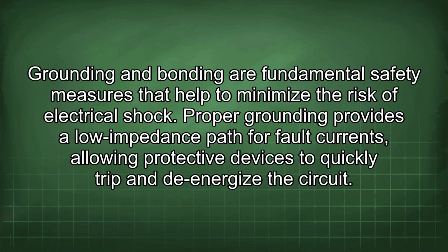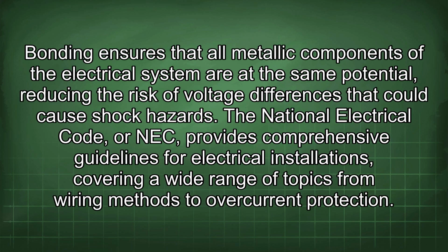Grounding and bonding are fundamental safety measures that help to minimize the risk of electrical shock. Proper grounding provides a low-impedance path for fault currents, allowing protective devices to quickly trip and de-energize the circuit. Bonding ensures that all metallic components of the electrical system are at the same potential, reducing the risk of voltage differences that could cause shock hazards.